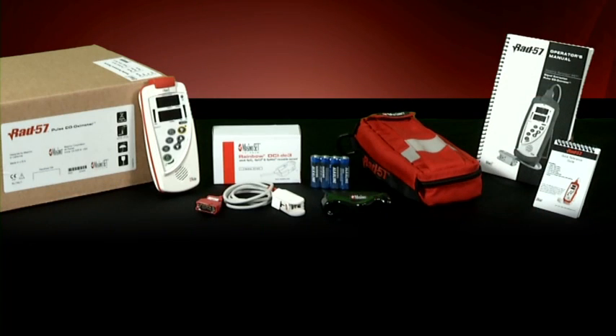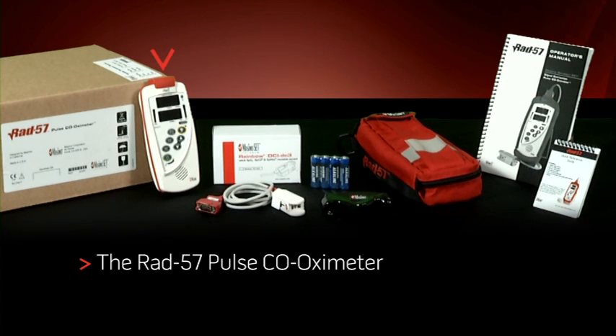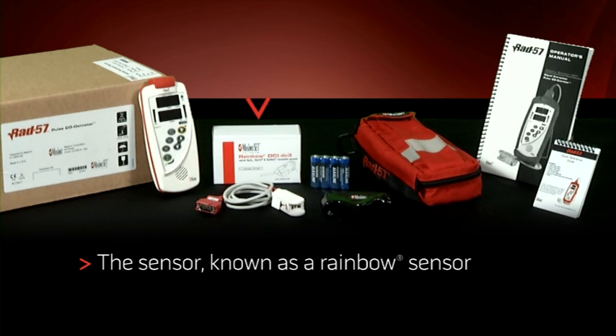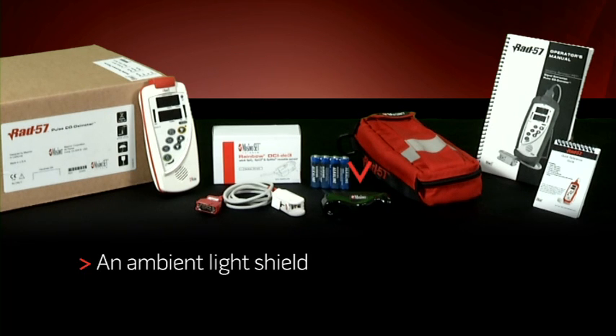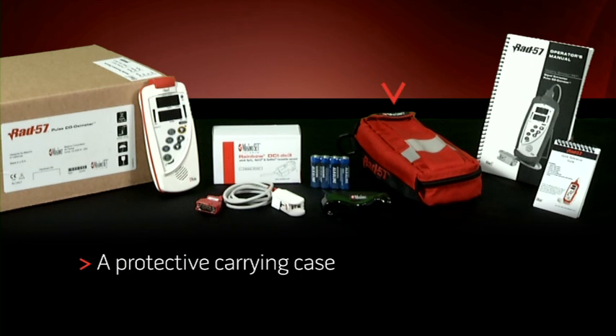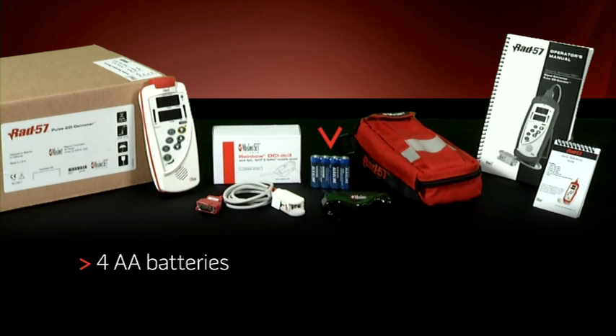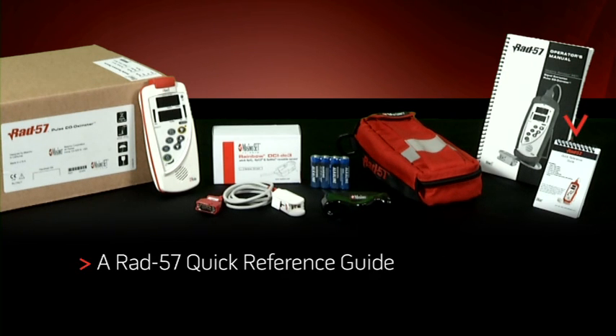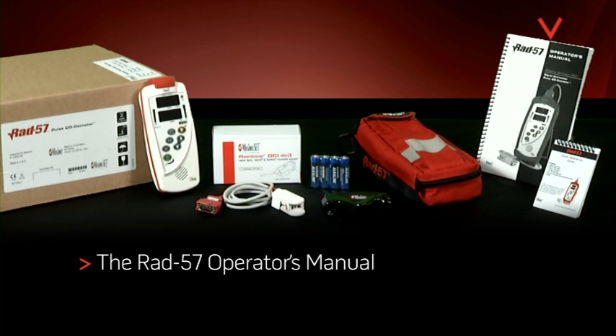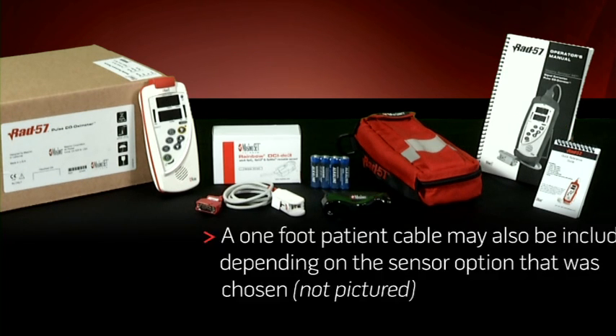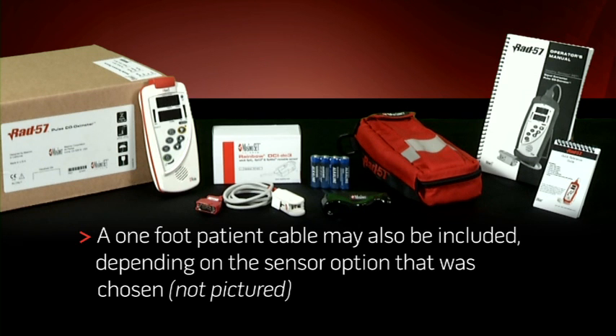First, begin by identifying the contents of the shipping carton: the Rad57 pulse co-oximeter, the sensor known as a rainbow sensor, an ambient light shield, a protective carrying case, 4 AA batteries, a Rad57 quick reference guide, and the Rad57 operator's manual. A 1-foot patient cable may also be included, depending upon the sensor option that was chosen. If you are missing any of these items, contact your Masimo sales representative.